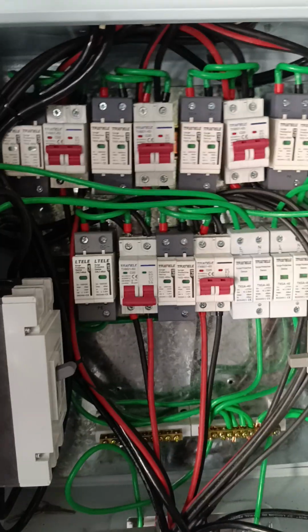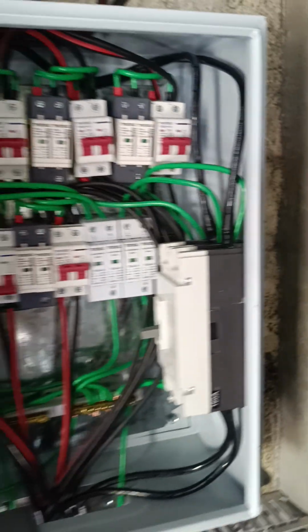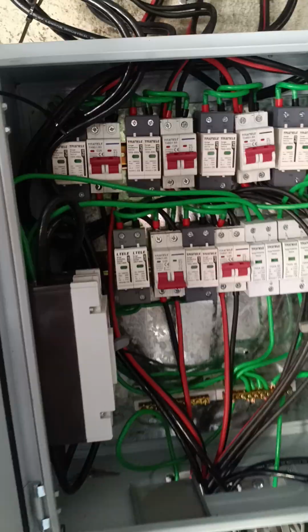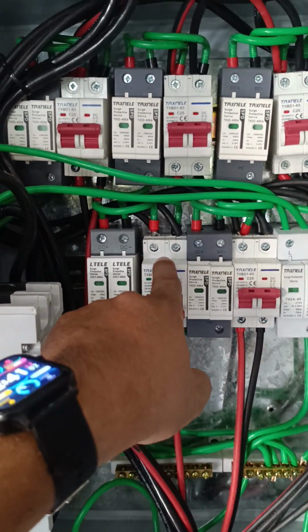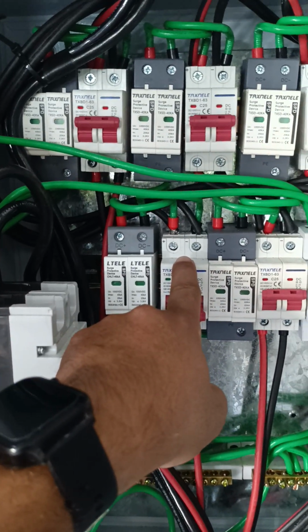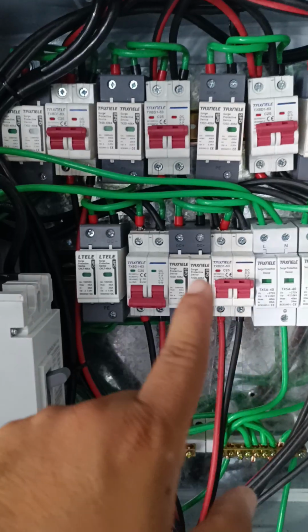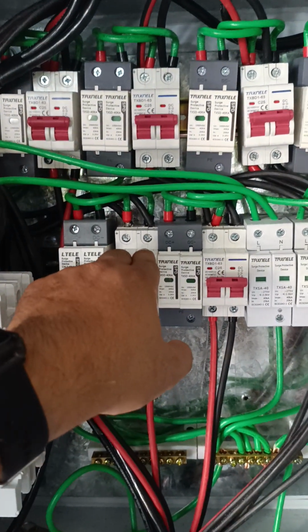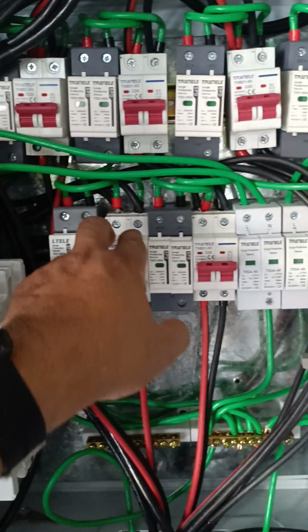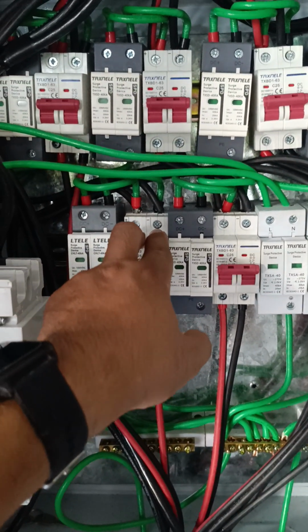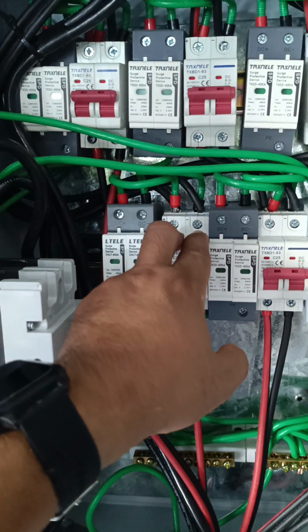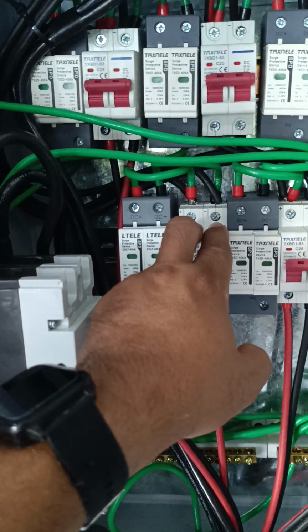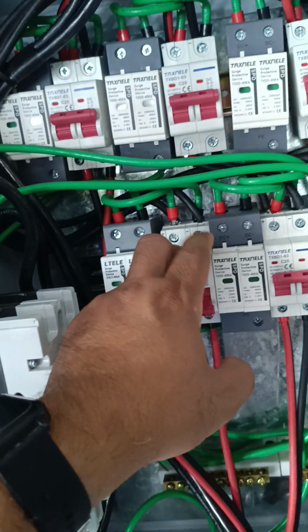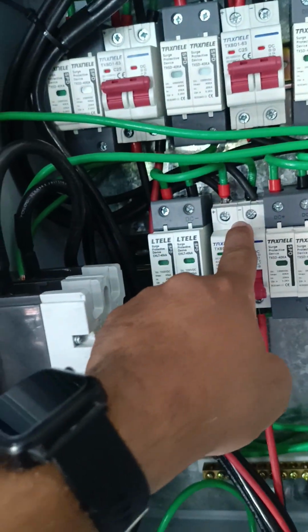So what we did was we went up there on the roof, and then we check one by one to isolate which string on top it belongs to this particular circuit breaker. So what we did was we one by one detach the MC4. Then here on the ground we tested this particular breaker, if there's still power coming in. If there's still power coming in, meaning the string that was detached does not belong to this breaker.